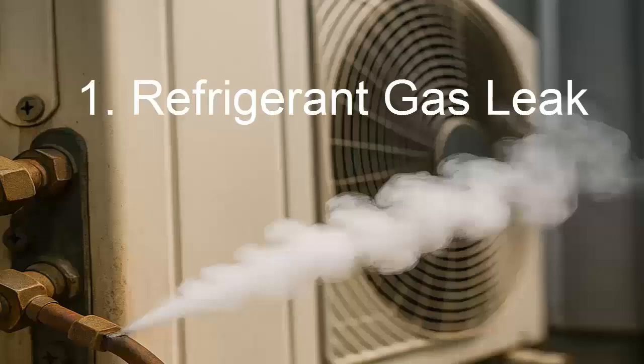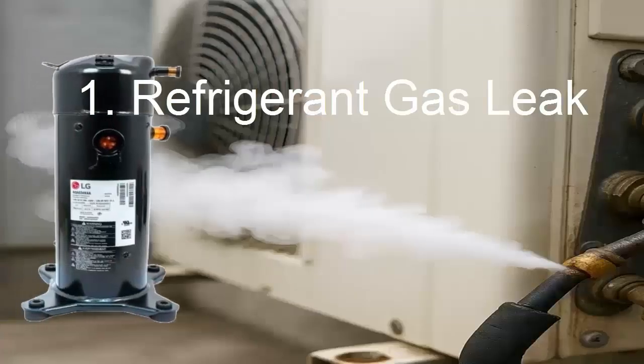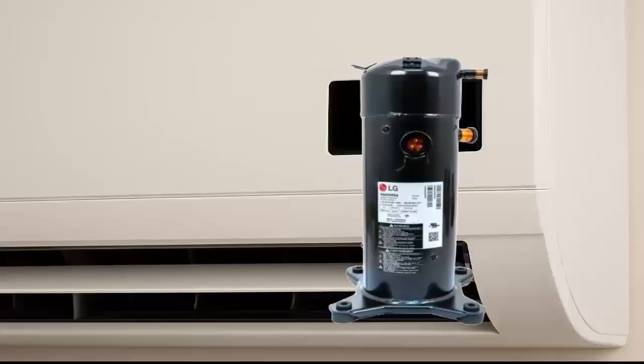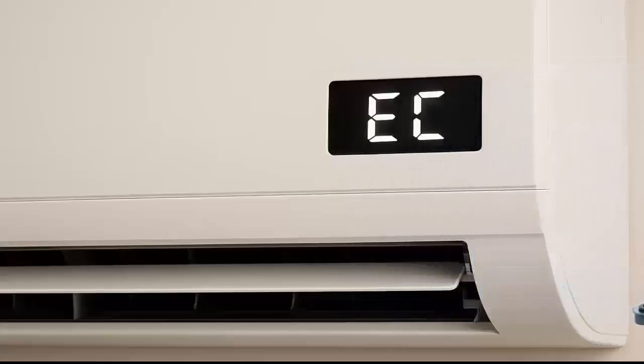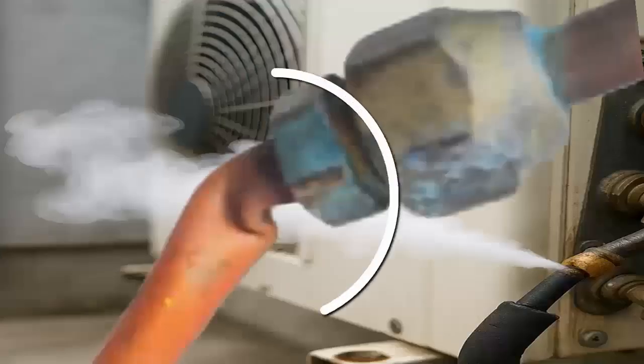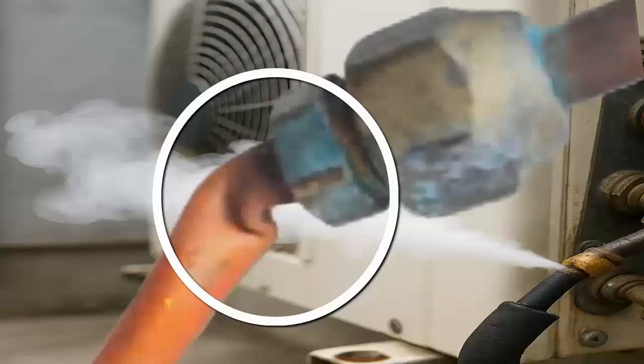Meaning number 1, and the most common one, is that code EC is related to refrigerant gas leakage, low charge, or insufficient refrigerant levels. This prevents the air conditioner from cooling properly, and can even damage the compressor if not detected or corrected in time. What causes it? Gas leaks can happen due to cracked pipes, loose valves, or simply wear and tear in the fittings, with small leaks developing over time.